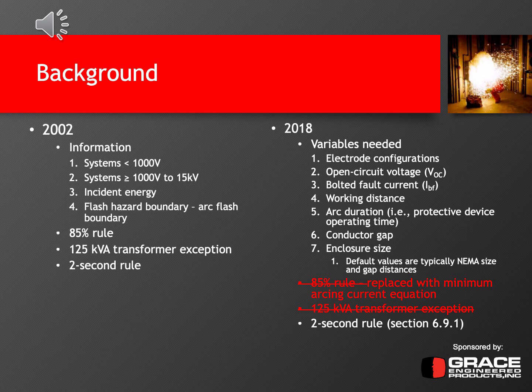The 2018 edition removed the 85% rule and replaced it with the minimum arcing current equation. So it's no longer a fixed 85%. Based on the system information and the configuration, there's now a minimum arcing current equation that needs to be calculated, which then gets put through the same rigor as the 85% current used to. The 125 kVA transformer exception was also eliminated from the 2018 edition. But the 2-second rule stayed, and it's in section 6.9.1.